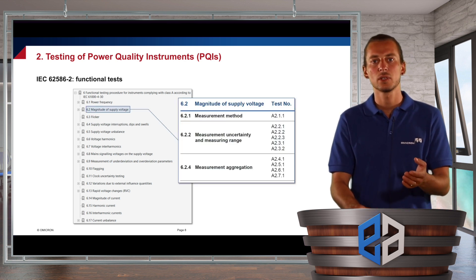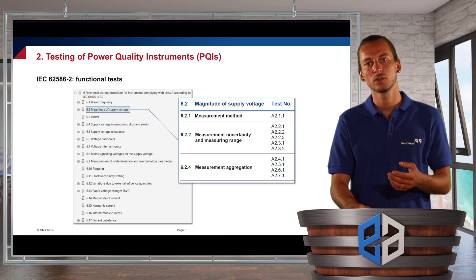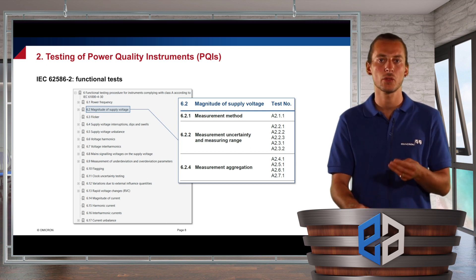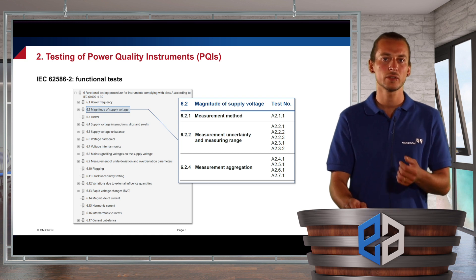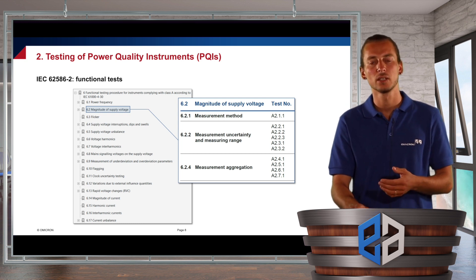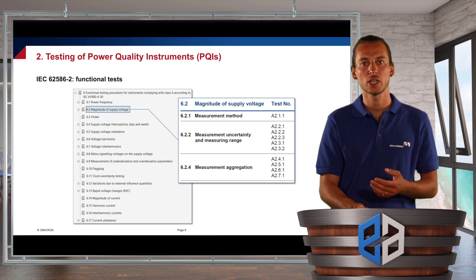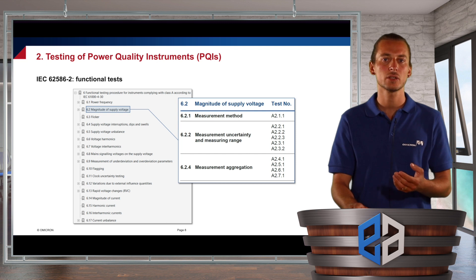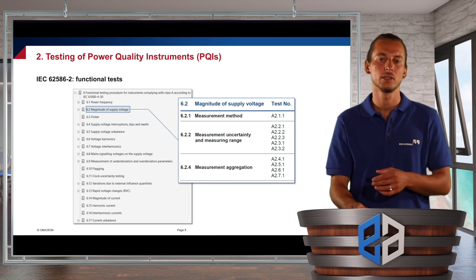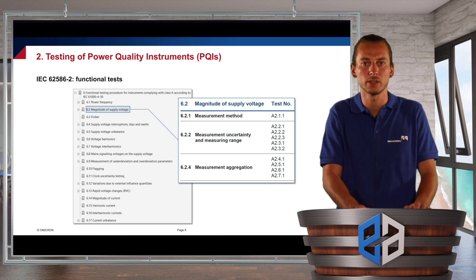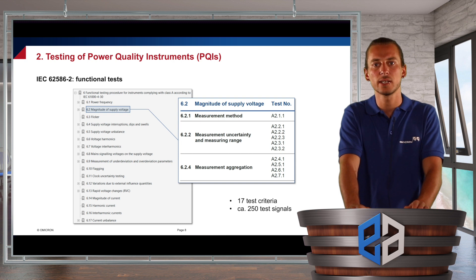For example, when we have a look on the magnitude of supply voltage tests, there are again several sub-chapters. Most of the times, there are three sub-chapters for each criteria. The first sub-chapter is checking for several measurement methods. The second sub-chapter is checking the measurement uncertainty over the full measuring range. And then in the third chapter, there are several tests for the aggregation of measurements. All in all, there are 17 test criteria and more than 250 test signals.